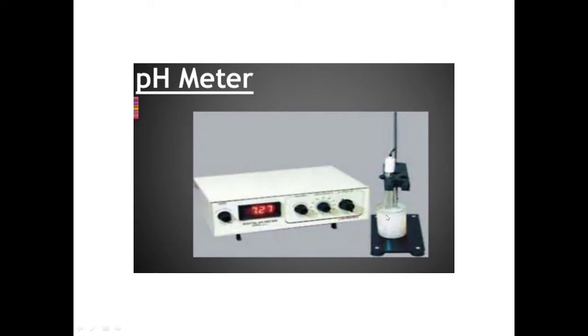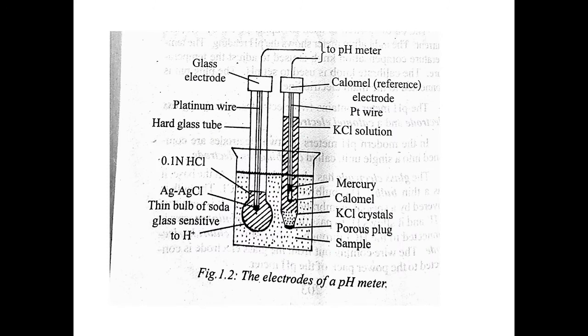This is a pH probe or pH electrode which is connected to the pH measuring unit. Okay, so it will measure and give you a display, like here it is showing 7.27. So the pH of the solution will be displayed on the display meter, or it may be a manually operated one. Now, originally, the pH meters that were used had two electrodes.